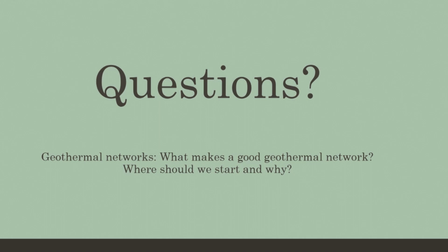Following up on what Mitch said, one thing we recommend is putting an electric resistance coil in your air source or ground-to-air heat pumps, which gives you backup power if the geothermal system goes down—so you'll have it there on the air side in the houses. As far as who else is funding these, a lot of colleges and universities are doing network systems on their campuses to gain energy efficiency and decarbonize those campuses.